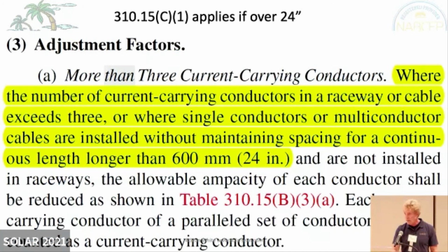There are these different adjustment factors in those steps, and that has to do with heat. If there's too much heat on a wire, you need a bigger wire or better insulation around that wire. Some things that cause heat are putting too many conductors in a small pipe. If I put 10 wires in there, it's like a 3-dog night. Those 3 dogs, that's what keeps you warm when you live in Alaska. So if you put more than 3 conductors in a conduit, I guess that'd be a 4-dog night, then you would create too much heat in there. And then also high ambient temperatures. There's another one that they got rid of: it used to be you'd have to derate for how high you were over a rooftop. And they got rid of that after the 2017 NEC came out.